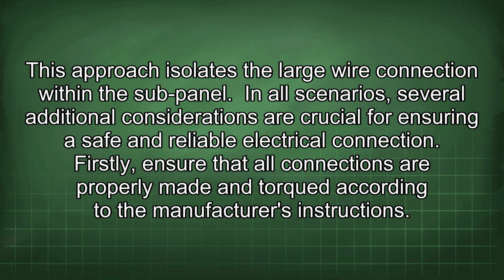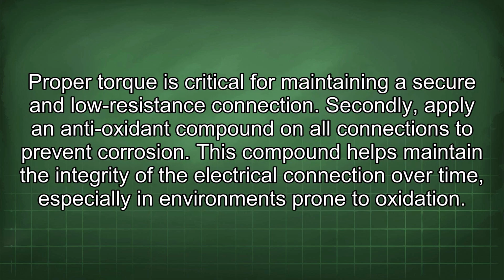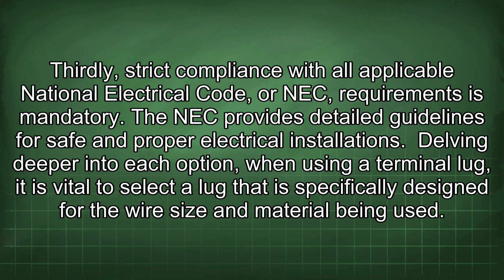In all scenarios, several additional considerations are crucial for ensuring a safe and reliable electrical connection. Firstly, ensure that all connections are properly made and torqued according to the manufacturer's instructions. Proper torque is critical for maintaining a secure and low resistance connection. Secondly, apply an antioxidant compound on all connections to prevent corrosion. This compound helps maintain the integrity of the electrical connection over time, especially in environments prone to oxidation. Thirdly, strict compliance with all applicable National Electrical Code, or NEC, requirements is mandatory. The NEC provides detailed guidelines for safe and proper electrical installations.